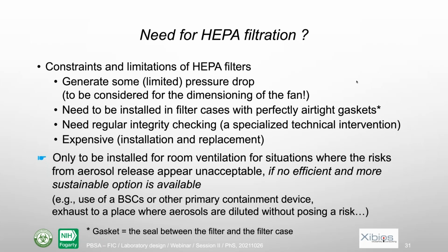Also, those filters are quite expensive, quite at installation, but also when you need to replace them. And if you are in a quite dusty environment, you will need to replace them quite often. And that means quite a lot of cost. Just to give you an indication, a third of the price of a Class 2 biosafety cabinet is the filters.